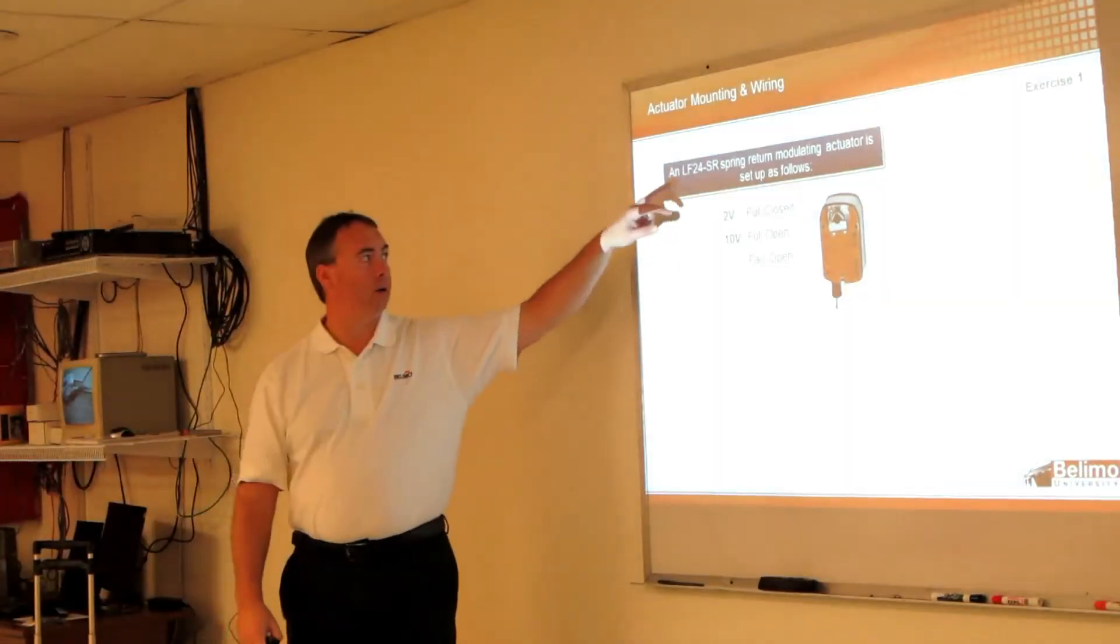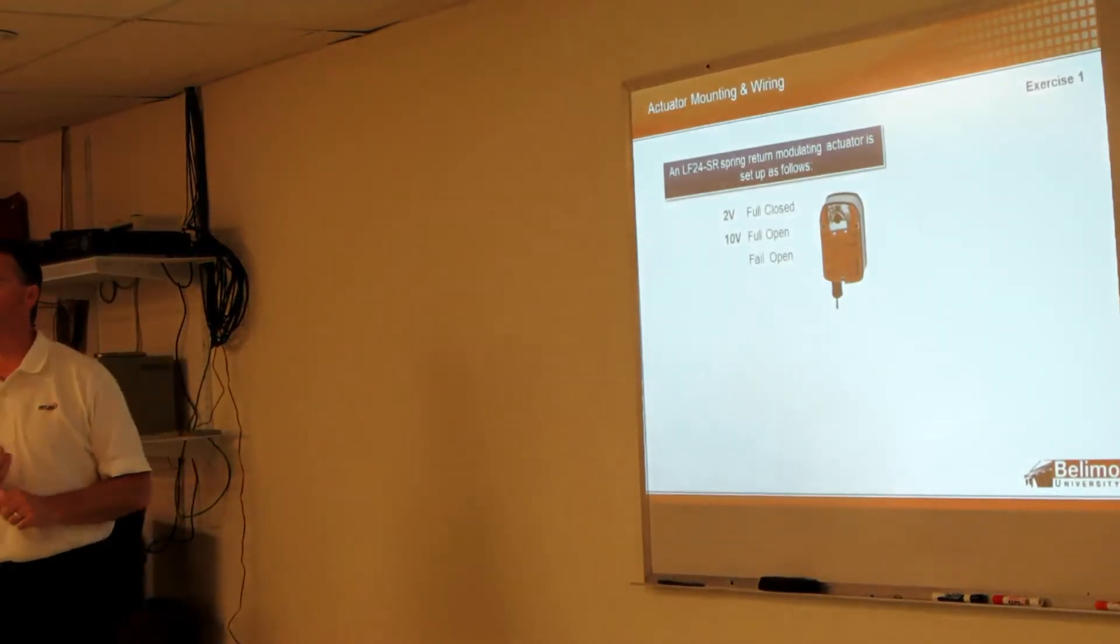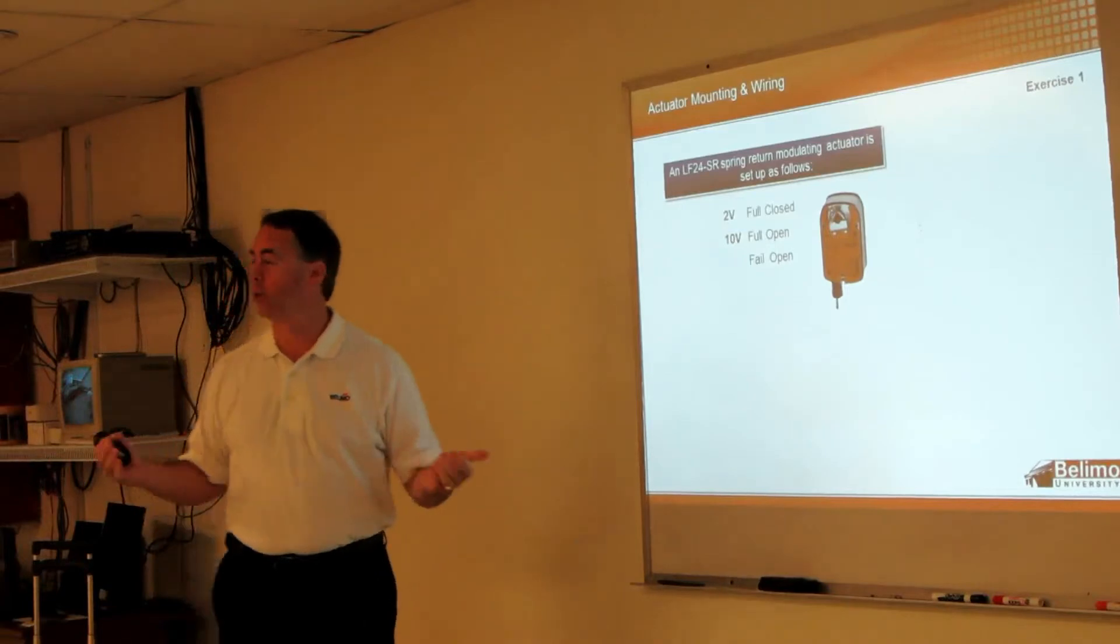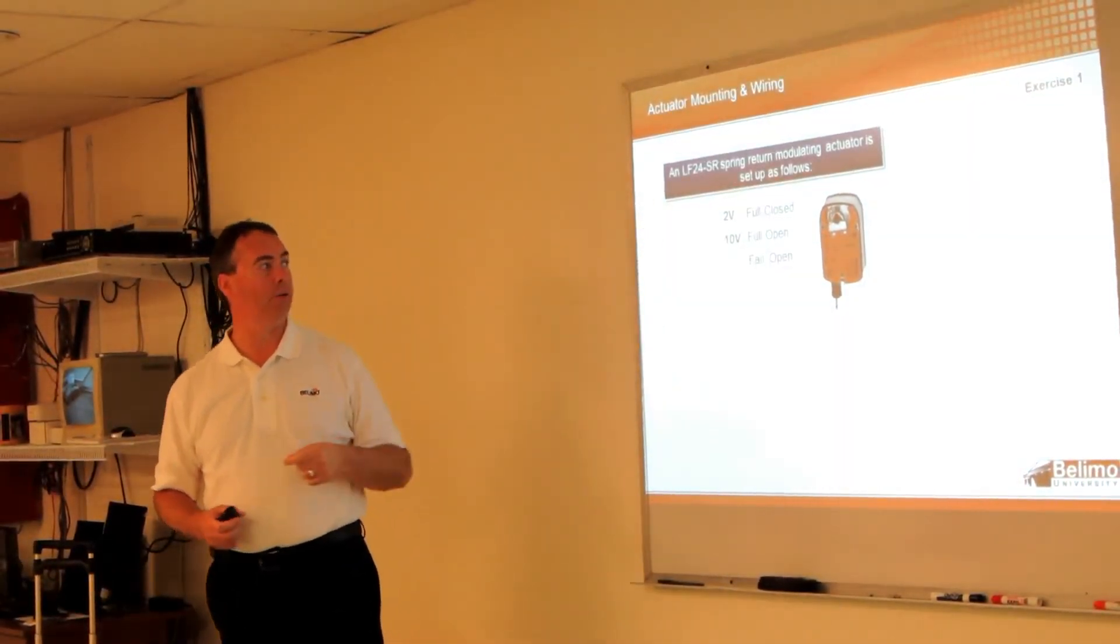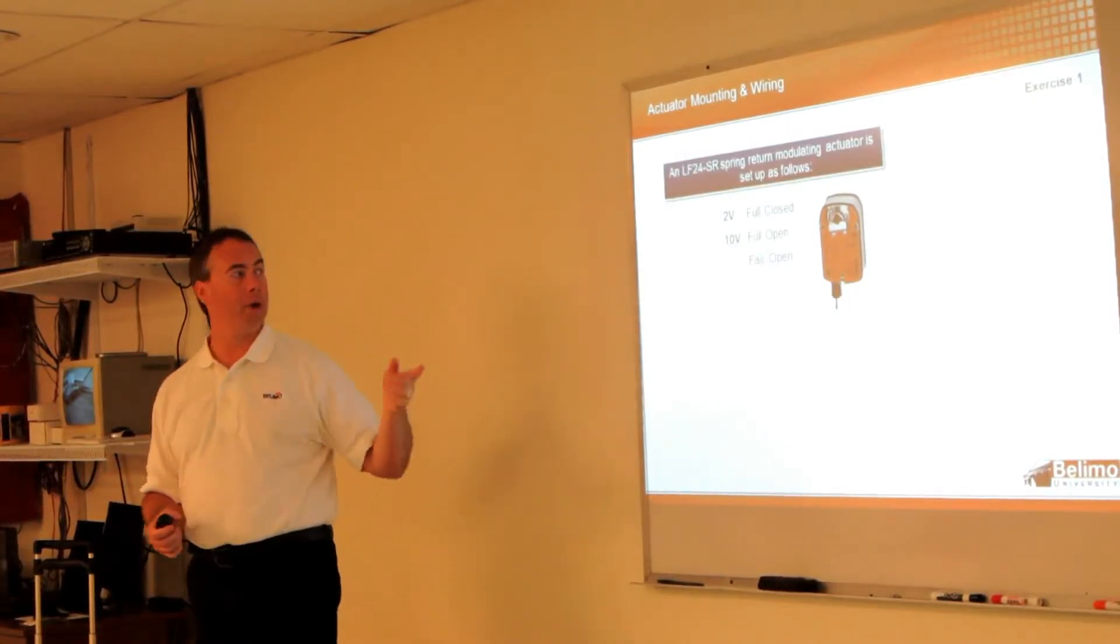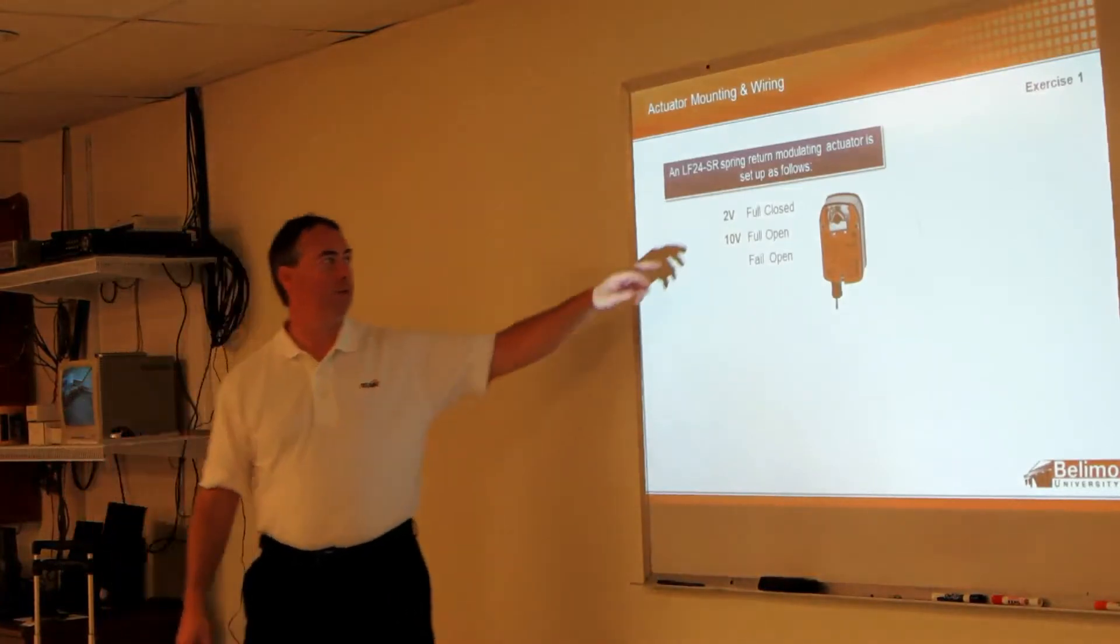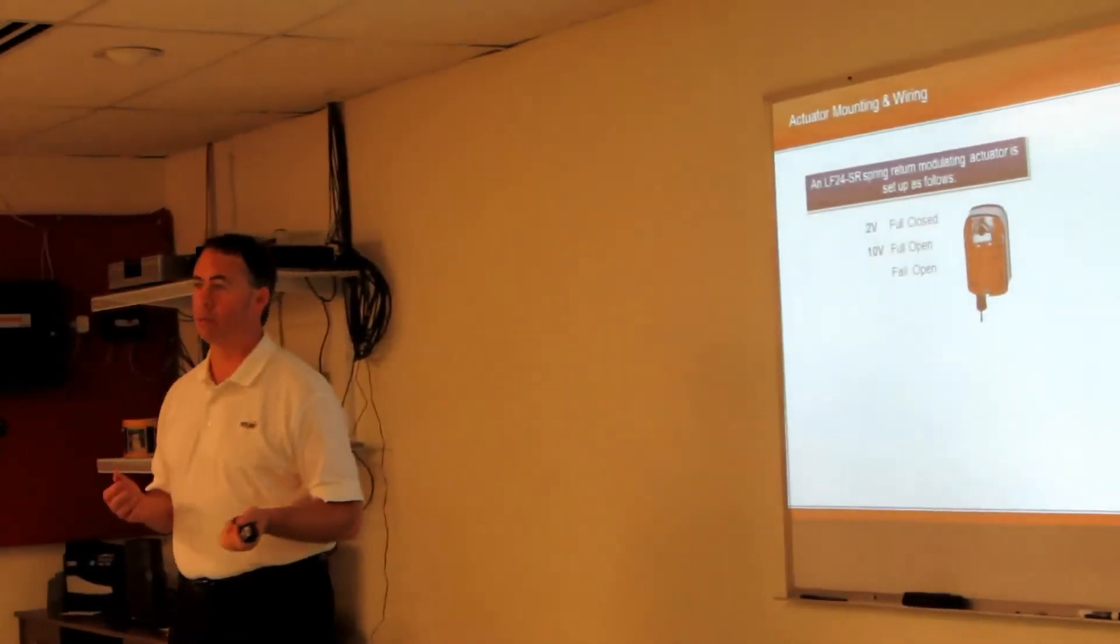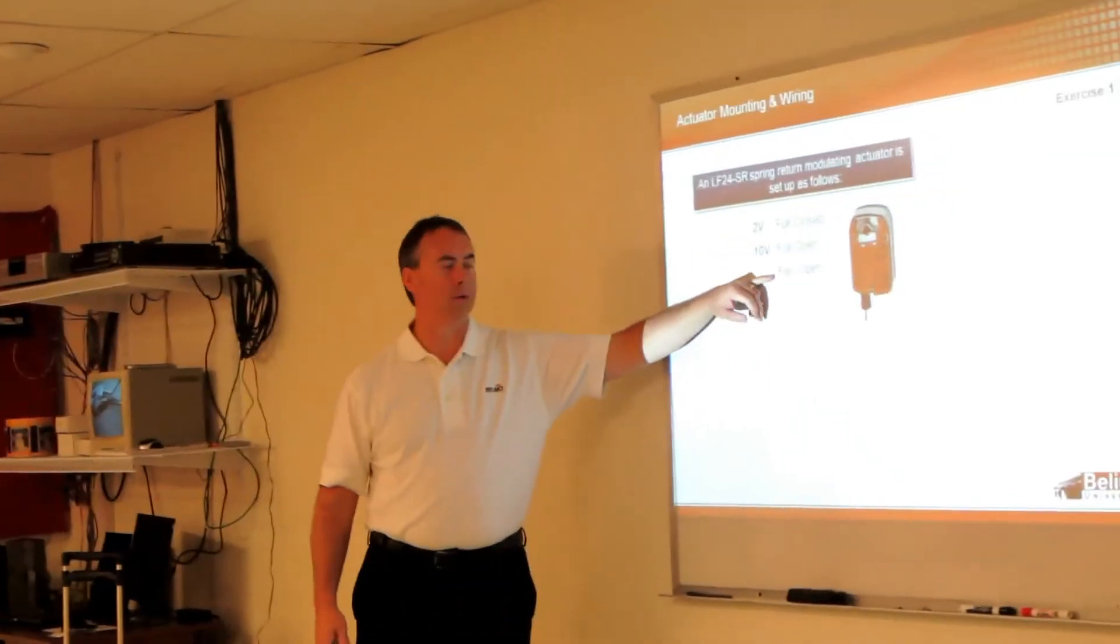So for example here we have an LF24-SR. We know that an LF is a 35 inch pound spring return. SR means it's a 2 to 10 volt control signal, set up with 2 volts fully closed, 10 open, and it's fail open. So that means if 2 volts is closed, that means it's a normally closed actuator. Normally closed, fail open.